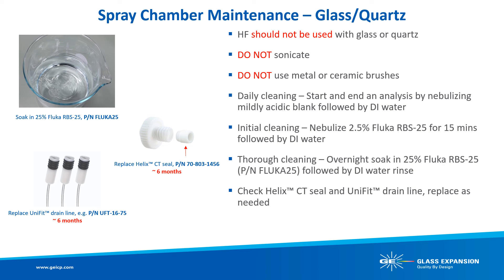Fluka RBS 25 is a laboratory-grade glassware cleaner that Glass Expansion sells in one-liter concentrate bottles; we highly recommend it and use it ourselves in our R&D and QC lab for cleaning all sample introduction components including nebulizers and spray chambers. Finally, every Glass Expansion spray chamber has consumable parts — while the spray chamber itself will last a very long time with good care, the Helix CT seal and Unifit drain lines should be checked and regularly replaced when necessary, approximately every six months.